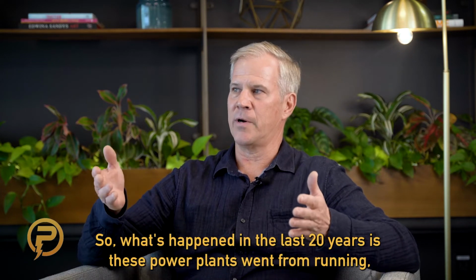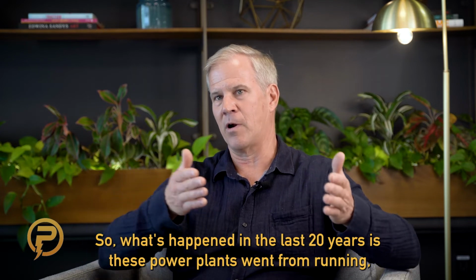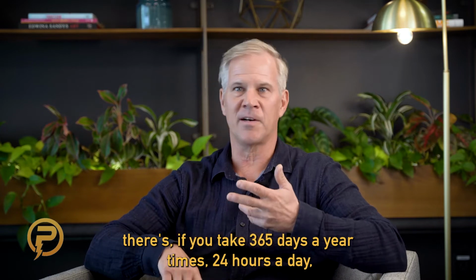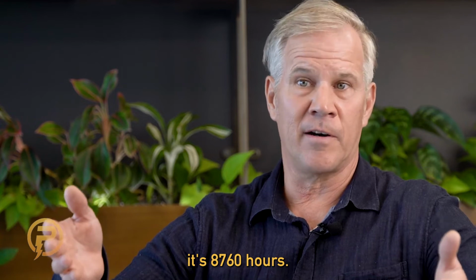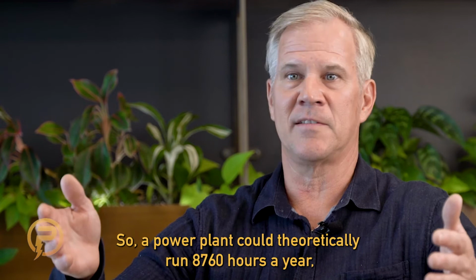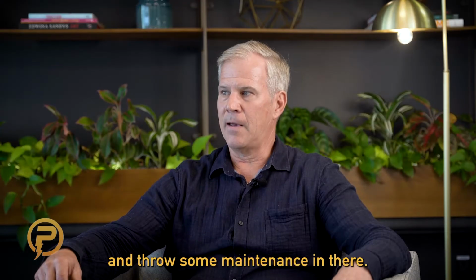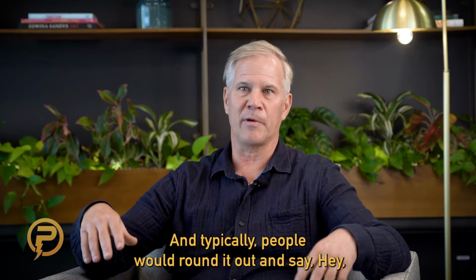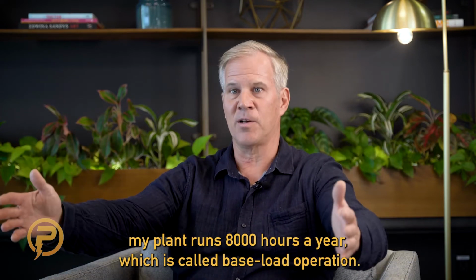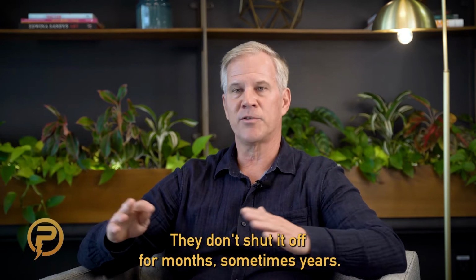So when I get this free carbon energy, can I actually use it? Is the challenge. So what's happened in the last 20 years is these power plants went from running, if you take 365 days a year times 24 hours a day, it's 8,760 hours. So a power plant could theoretically run 8,760 hours a year, and throw some maintenance in there. And typically people would round it out and say, hey, my plant runs 8,000 hours a year, which is called base load operation. They turn that thing on, they don't shut it off for months, sometimes years.